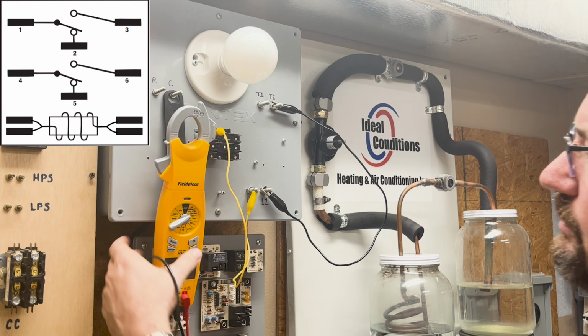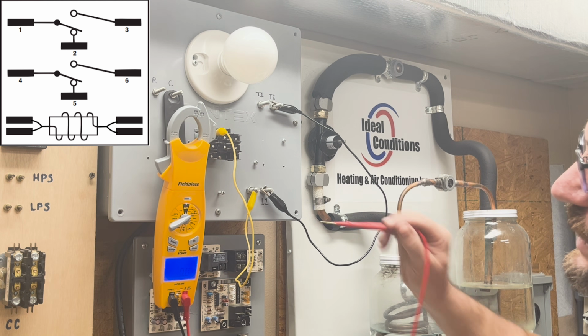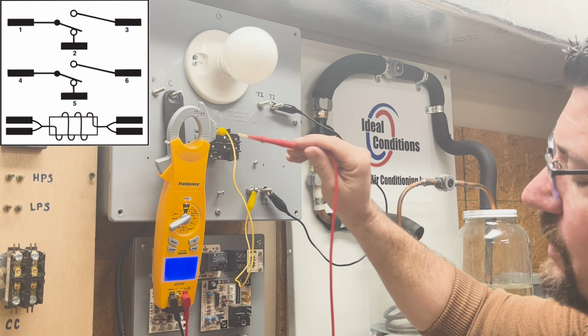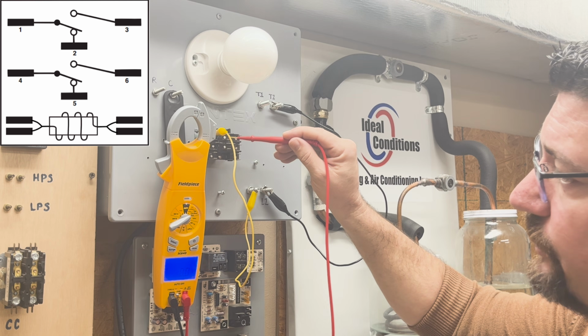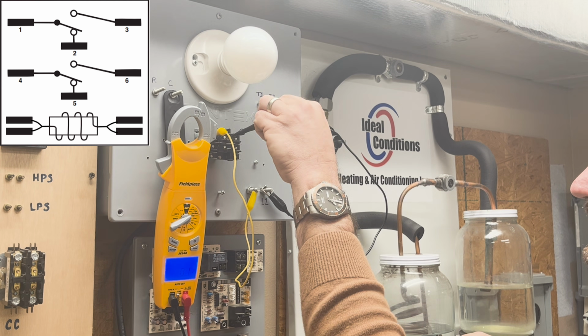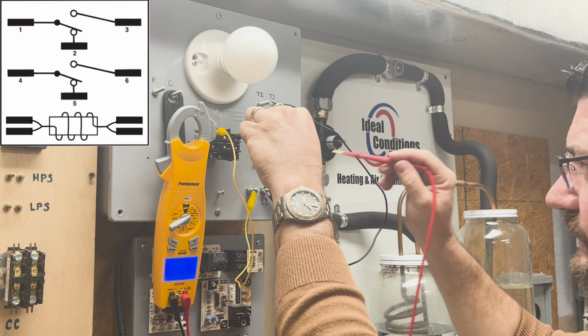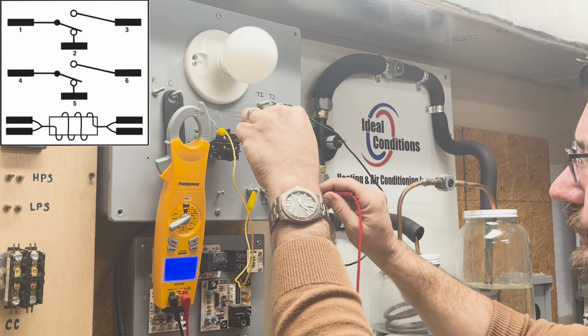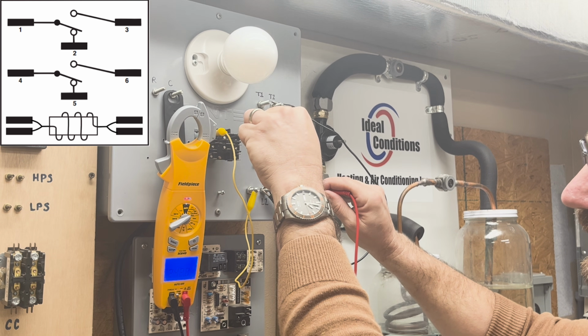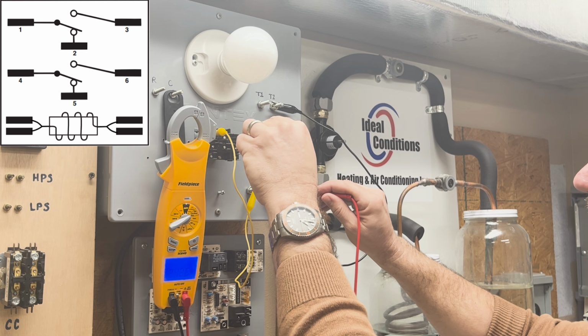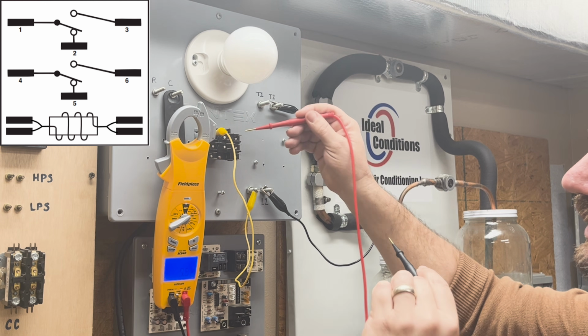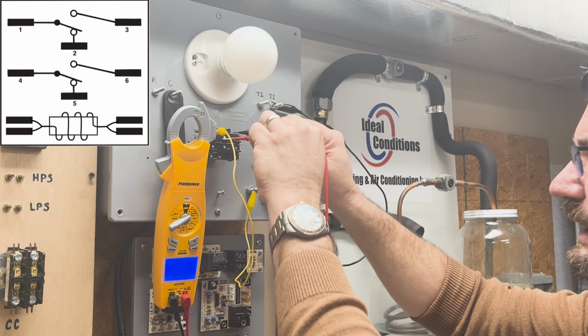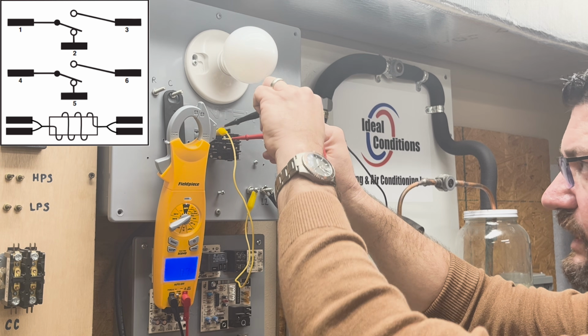So I'm going to put my backlight back on my meter, and as you can see, I don't have any voltage, or I'm sorry, any wires landed on terminal 2 here. But if I put my lead on terminal 2 and I came back over here to L2, you'll read that I have 242 volts. But if I came over here and I put a lead on terminal 2 and a lead up here on 1, I read 0.